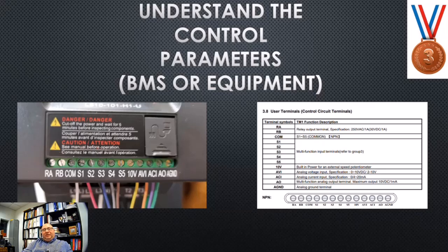You could take your output and feed it to a BMS system or another motor that could actually run off this VFD drive, and this would be the ground to that terminal block. So this ground is shared between 10, AVI, ACI, AO, and ground. And then this terminal here, 5, 4, 3, 2, 1, and common are shared together on that terminal block.